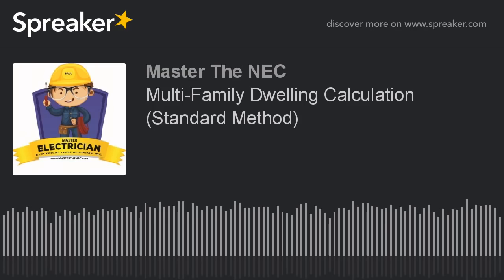If you're doing a calculation for a single family dwelling, it's really just this simple. You don't have the number of units to multiply it by. You just have the one unit to multiply it. Now, you might have other things in there. You might have a dishwasher. You might have a disposal. You'll have more appliances. And if you have 4 or more, you still get to apply the fixed and fastened in place appliances application in 220.53, which results in the 75% demand factor. You just don't have 18 units. You just have 1 unit.